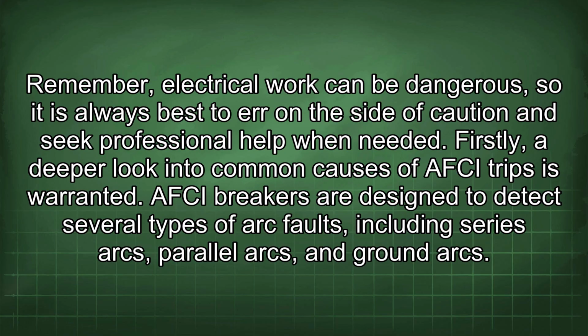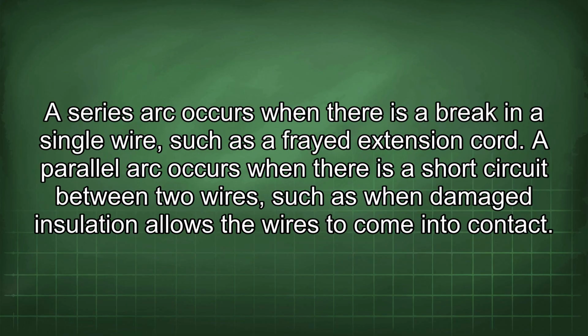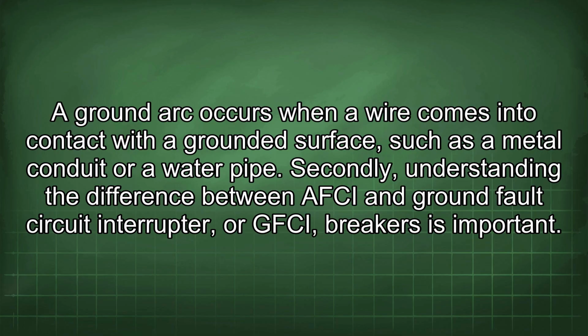Firstly, a deeper look into common causes of AFCI trips is warranted. AFCI breakers are designed to detect several types of arc faults, including series arcs, parallel arcs, and ground arcs. A series arc occurs when there is a break in a single wire, such as a frayed extension cord. A parallel arc occurs when there is a short circuit between two wires, such as when damaged insulation allows the wires to come into contact. A ground arc occurs when a wire comes into contact with a grounded surface, such as a metal conduit or a water pipe.